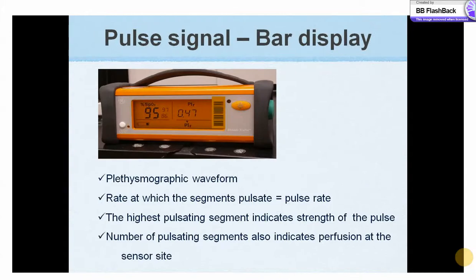When the pulse is presented as bar graphs, the rate at which the segments pulsate equals the pulse rate. The highest pulsating segment indicates the strength of the pulse, and the number of pulsating segments also indicates perfusion at the sensor site — the more segments, the stronger the perfusion. If the bar display is less than 50 percent, it indicates poor quality signals.